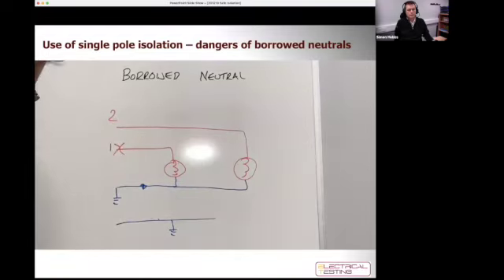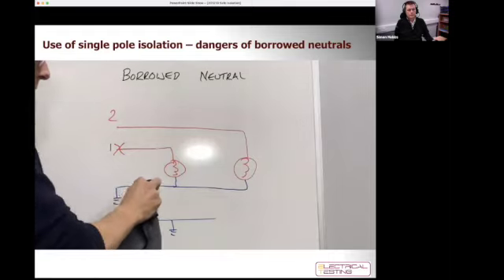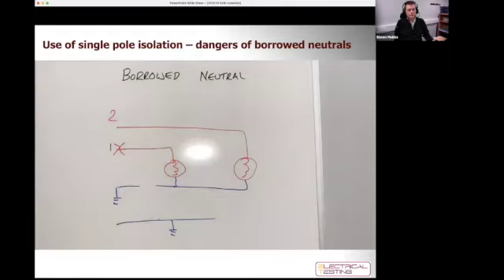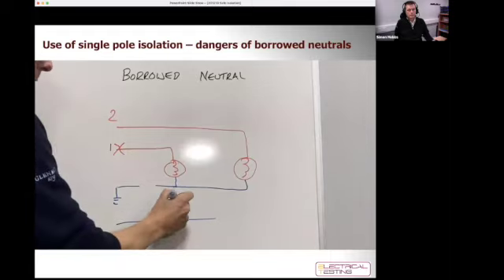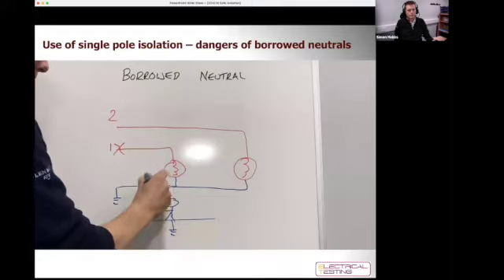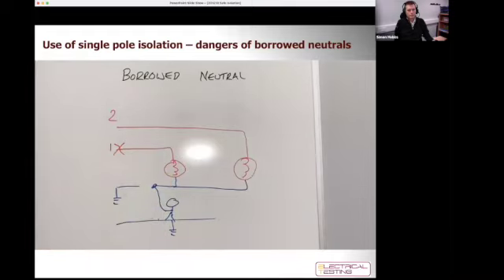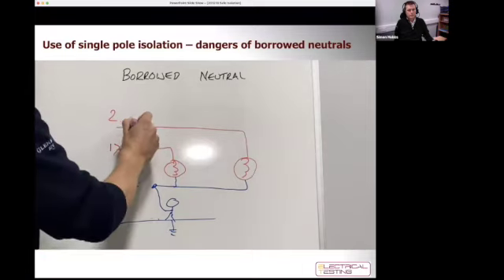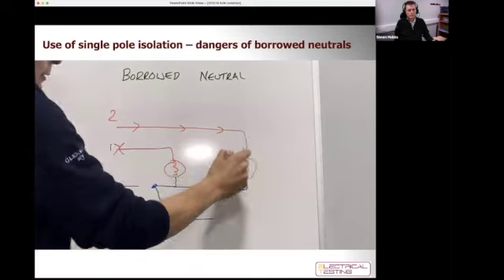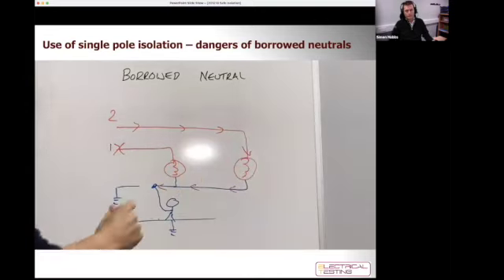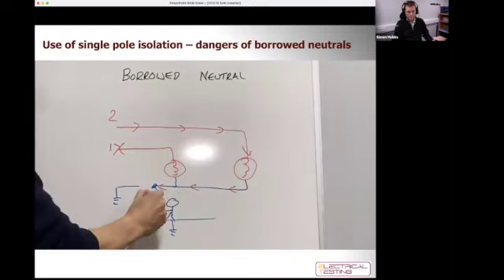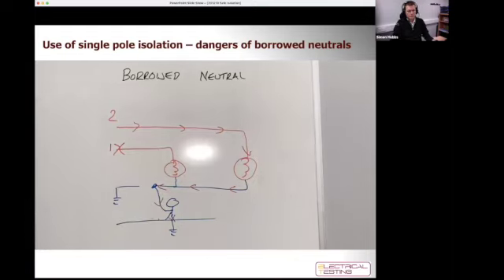But what we'll see here is that circuit 2 is still energized. And the problem occurs with a borrowed neutral when we start disconnecting components or cutting through cables because we believe it's isolated. If I'm now doing my work at this point, having disconnected equipment, assuming and suspecting that it's dead, I've isolated, I've locked off, all the things we've talked about previously, current is still flowing through circuit 2, and unfortunately it's got nowhere to go on its return path, so it goes through me back to earth, and that's the danger of borrowed neutrals.